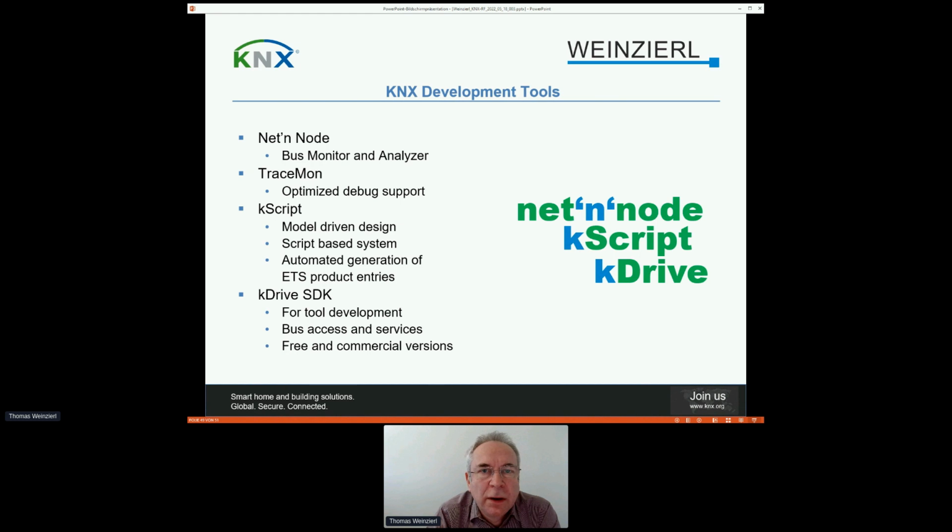That's why we can write down the structure of your application in a Python syntax, and we can create in an automated way the complete ETS product entry. This integrates the static part as well as the complete dynamic part and also the translations. In parallel, we create a couple of include files which hold all the addresses and names of parameters, group objects, and so on.